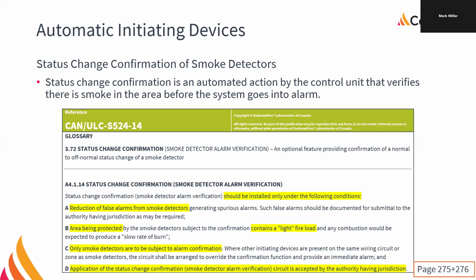Great idea. And of course, one of the things they were doing was staff training for emergencies. Great idea. Let's do the training. And so they decided to do, among other things, training for what if there's a fire in one of the recovery rooms in maternity, right? So you've got mom and new baby right there. What if a fire breaks out? What do we do? They have their procedures, but they wanted to test it. And so the maintenance manager borrowed a can of smoke from me, and they went up to test it, and they couldn't get the smoke detector to activate. The smoke detector worked. We'd verified it the week before. They could not get the smoke detector to activate because of the status change confirmation. They actually tried, and I was not happy they tried this because it's a bad idea.